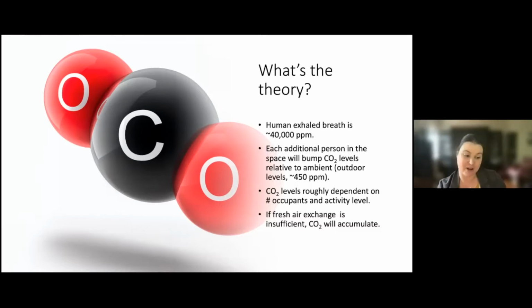Depending on the number of occupants and their activity level, the amount of CO2 in the space should scale upward pretty reliably with occupancy. If there's no ventilation, or ventilation that's just insufficient, CO2 will accumulate. So the upward trend is the red flag.